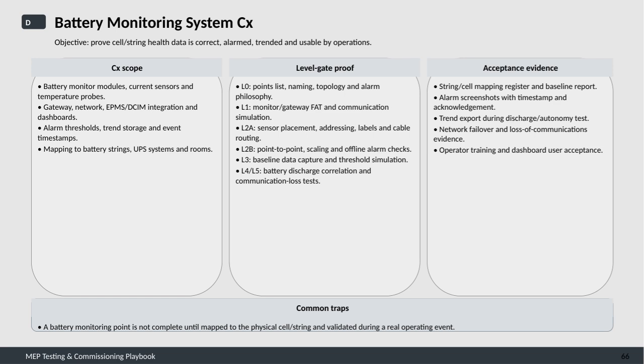When it comes to level gate proof, there are multiple layers of testing. First, we confirm that the points list, naming conventions, topology, and alarm philosophy are all in place at level 0. Then, at level 1, we conduct factory acceptance tests on the monitors and gateways, simulating communications. Level 2A focuses on sensor placement, labeling, addressing, and cable routing, while 2B checks the accuracy of point-to-point connections, scaling, and offline alarm functionality. Level 3 is about capturing baseline data and simulating threshold alarms. And finally, levels 4 and 5 involve validating battery discharge correlation and testing for communication loss.